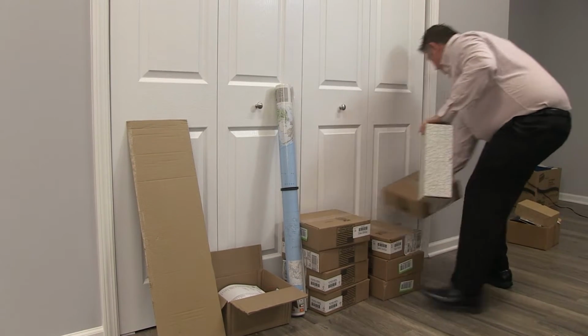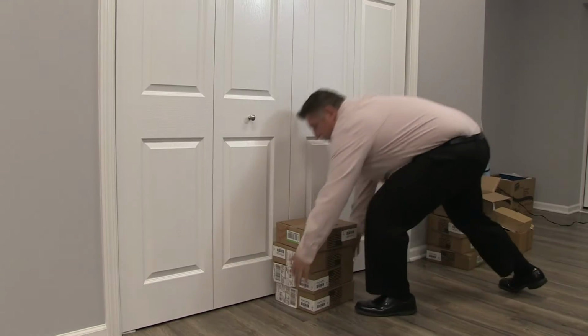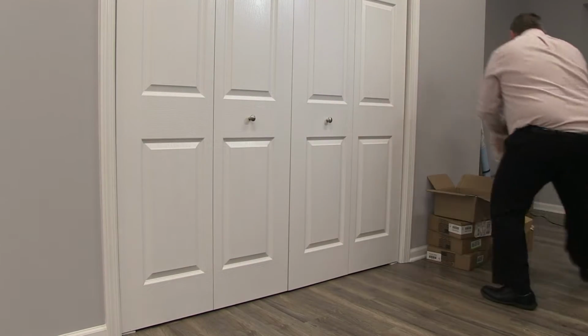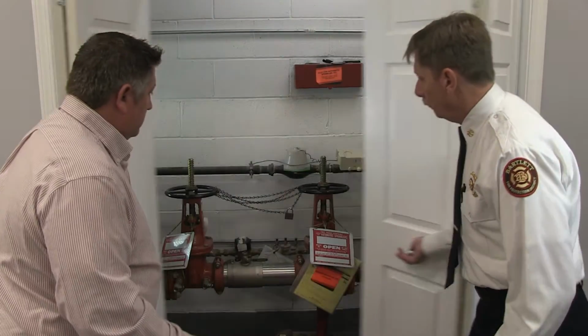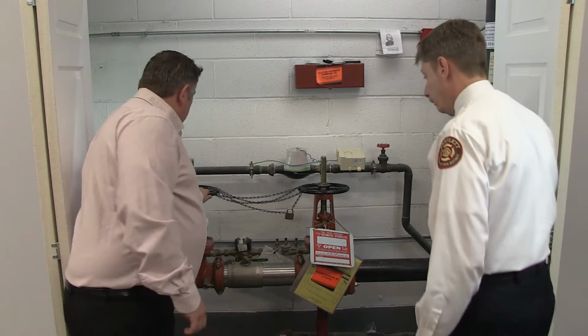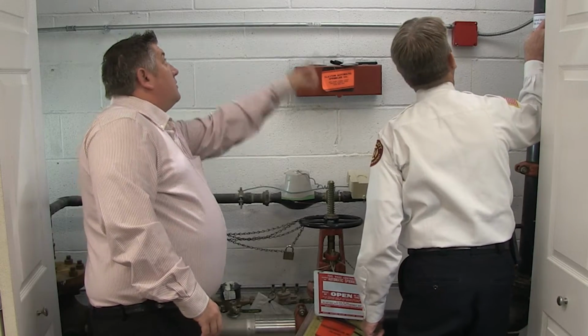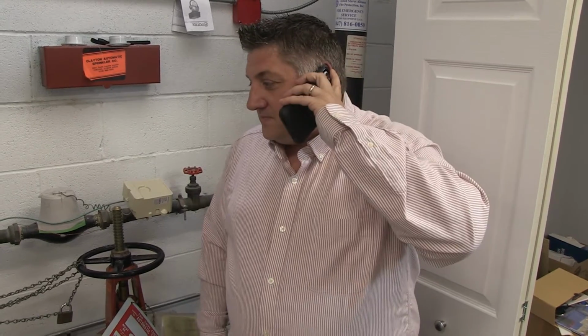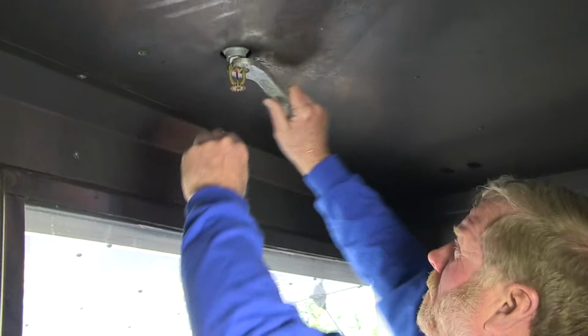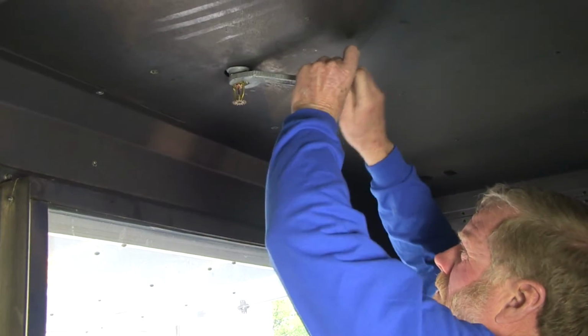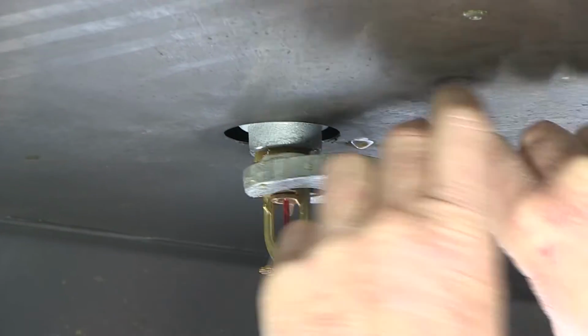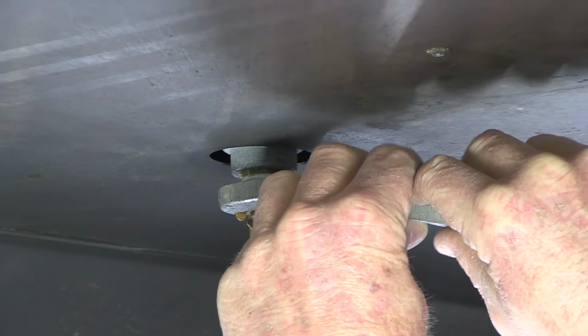You will want to make sure all components of your fire sprinkler system are easily accessible at all times, so be sure there are no impediments or obstacles that prevent you or qualified personnel from conducting ITM activities. If for some reason you must test or shut down the system or its supply, you must first notify the authority having jurisdiction, the fire department, and the alarm receiving facility. Provide them with the purpose for the shutdown or test, the components involved, the estimated time at which it will be fixed, and the expected duration.